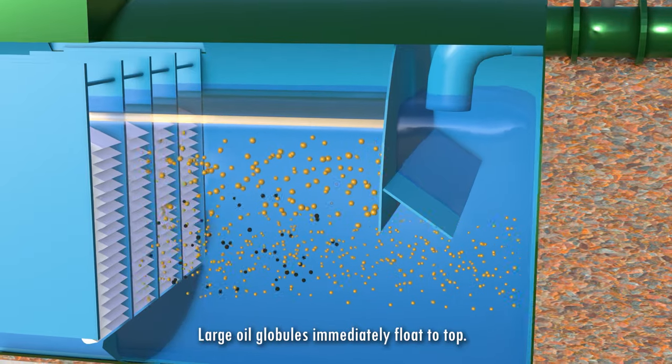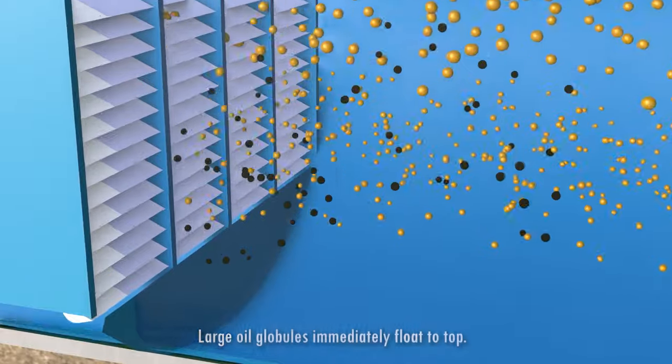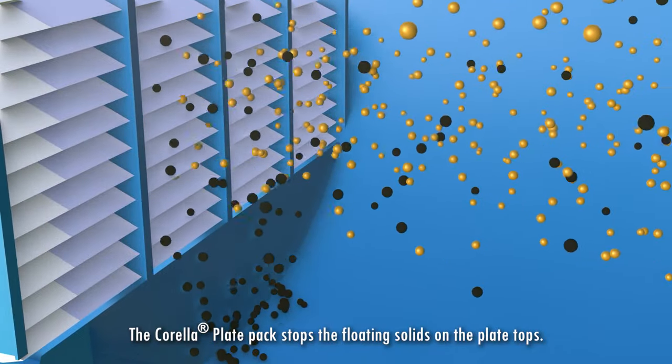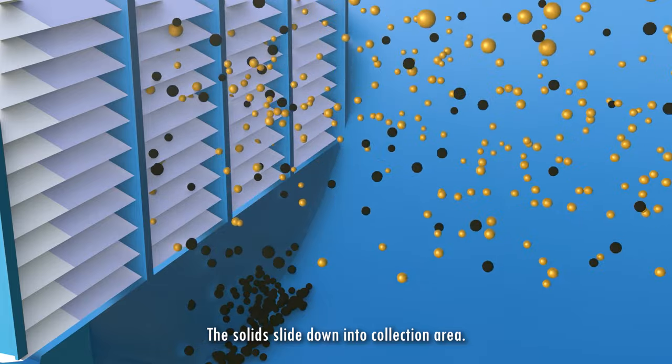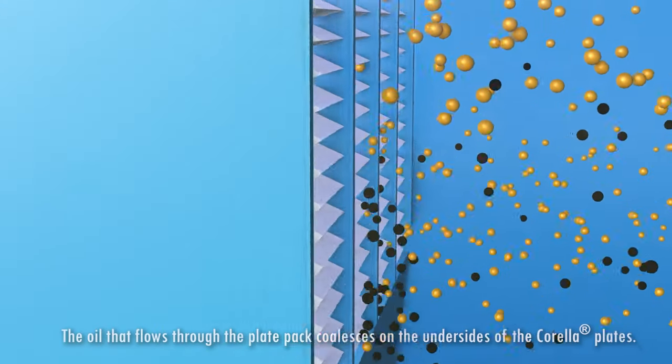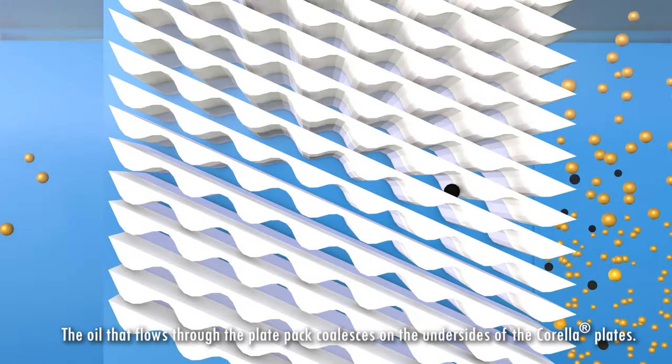As we move through the tank, large droplets float to the top of the water and the smaller particles move through the corella plates. Now they're flat on top and corrugated in the bottom, so solids that hit the flat top slide down and sink to the bottom.